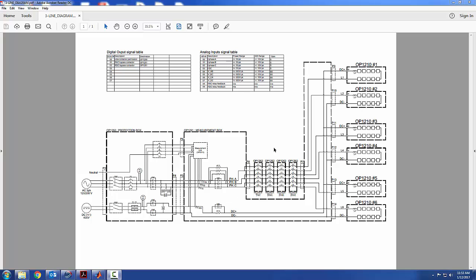Then you have the arm inductance modules—here four are shown, but you can have different numbers depending on your needs. Then you have the OP1210 units connected directly to the measurement unit and the arm inductance units. Here's the standard setting with six OP1210 units making 10 submodules per valve for a total of 60 submodules for a three-phase MMC converter.